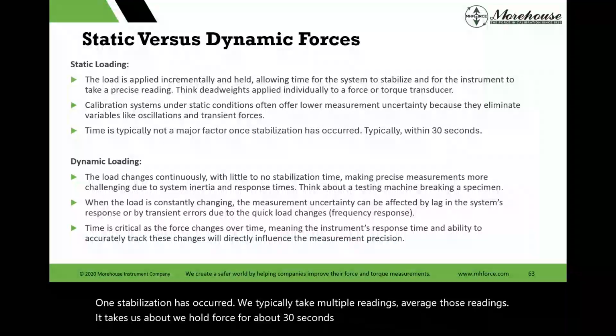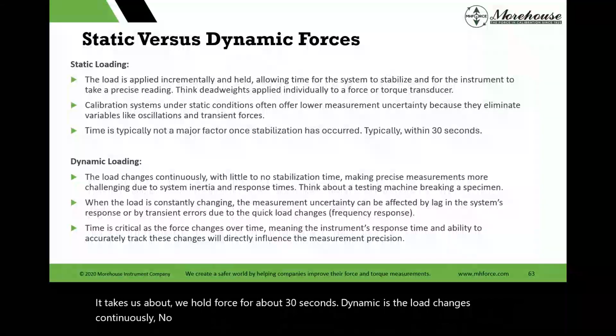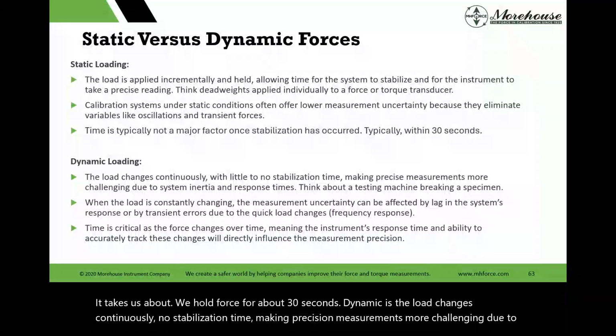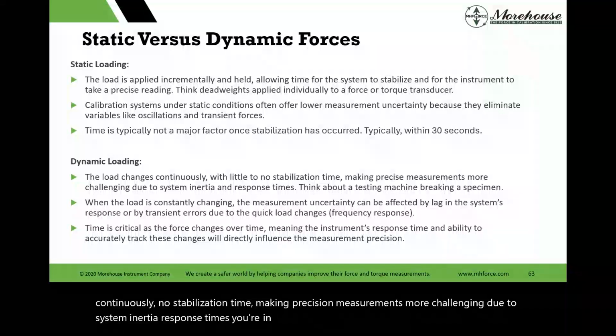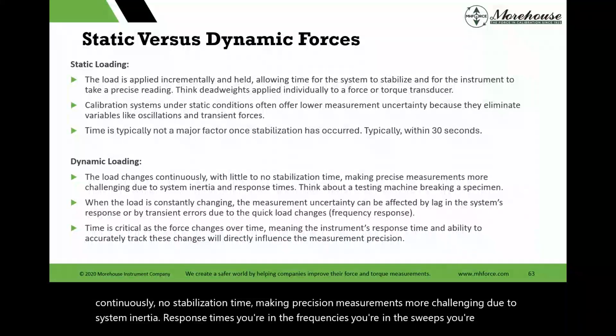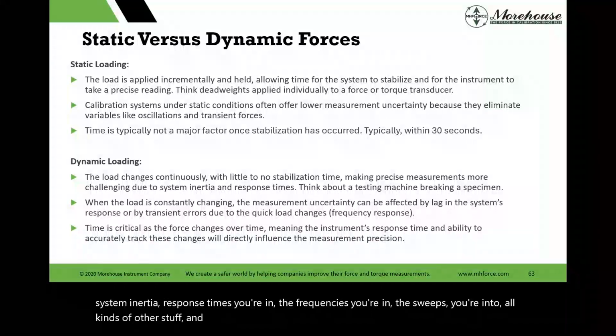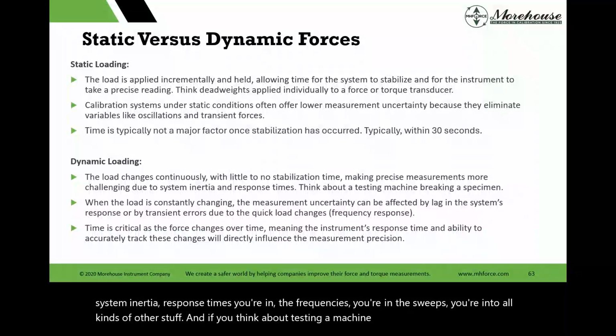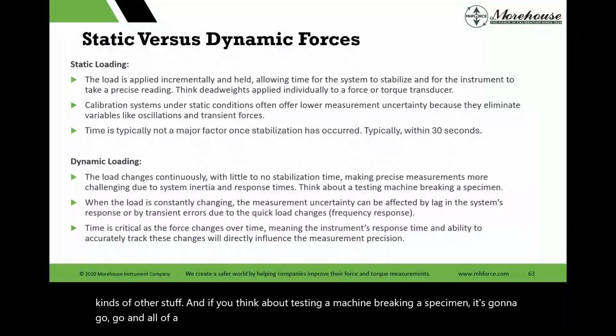Dynamic is where the load changes continuously. No stabilization time, making precision measurements more challenging due to system inertia and response times. You're into frequencies, you're into sweeps, you're into all kinds of other stuff. And if you think about testing a machine, breaking a specimen, all of a sudden it's going to break. So the load on that thing is constantly changing.